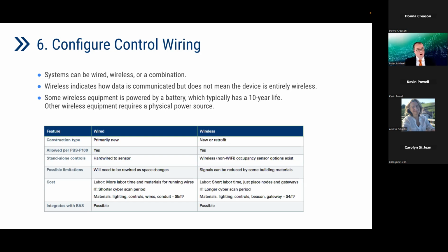The advantage with wireless is it's wireless - you don't have to run all the communication wires, but your IT mitigation may take longer because there are more wireless protocols that have to be managed than in a possible wired situation. Wired probably still requires some IT mitigation if you're using a network system, so you can't just say you don't have to worry about that. In both scenarios, you could probably integrate with a building automation system. Next slide, please.